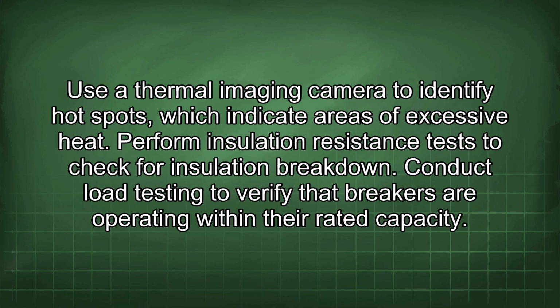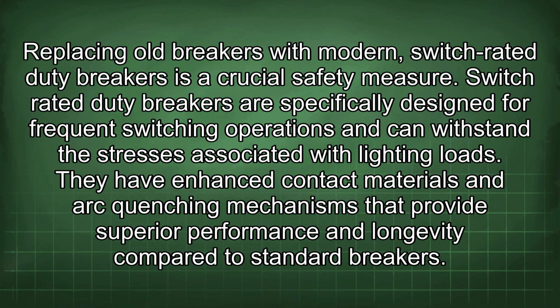Use a thermal imaging camera to identify hotspots, which indicate areas of excessive heat. Perform insulation resistance tests to check for insulation breakdown. Conduct load testing to verify that breakers are operating within their rated capacity. Replacing old breakers with modern, switch-rated duty breakers is a crucial safety measure.